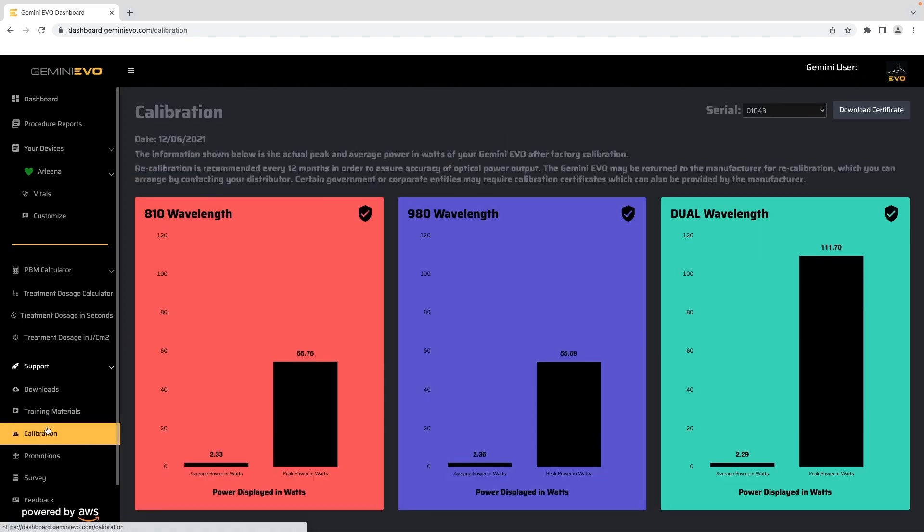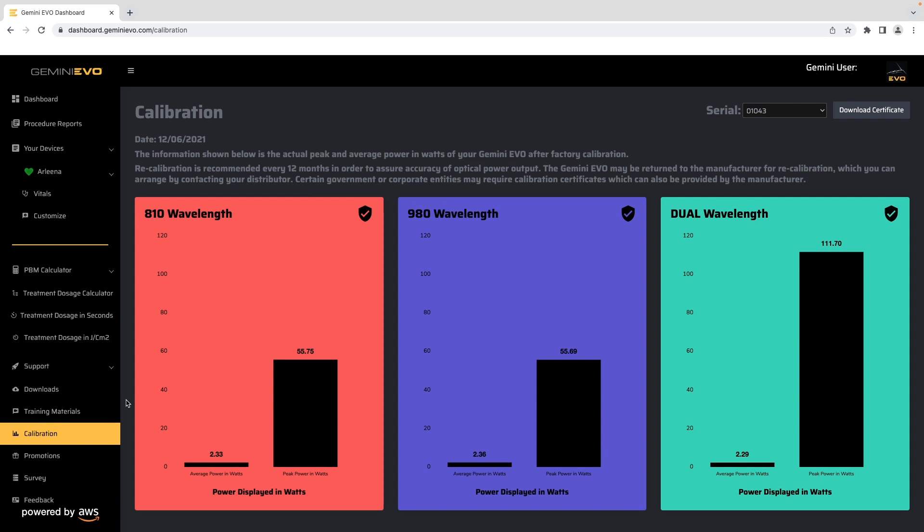The calibration section displays your unit's peak and average power in watts from the last factory calibration. Certain government or corporate entities may require calibration certificates, which can also be provided by the manufacturer and can be accessed and downloaded from this section.